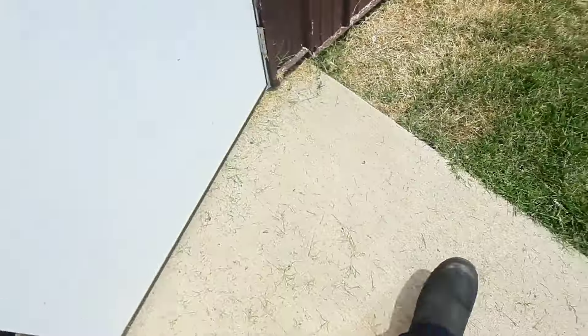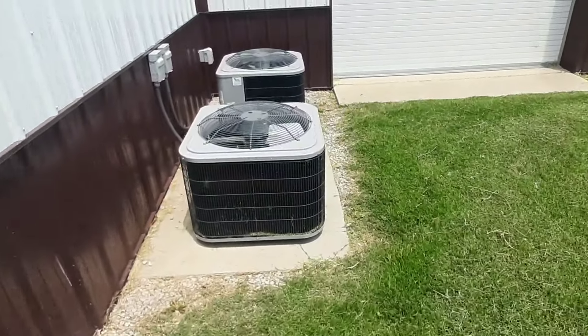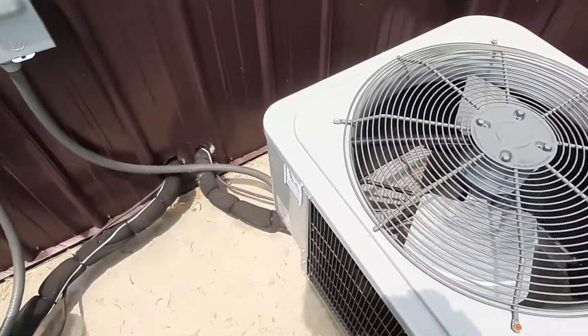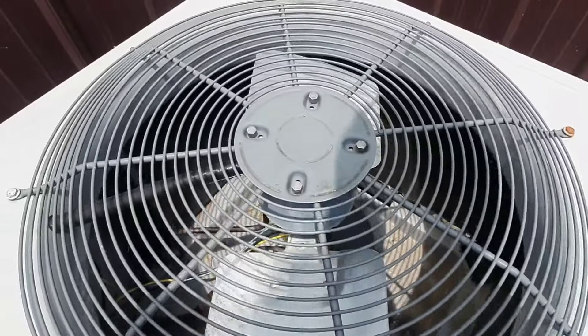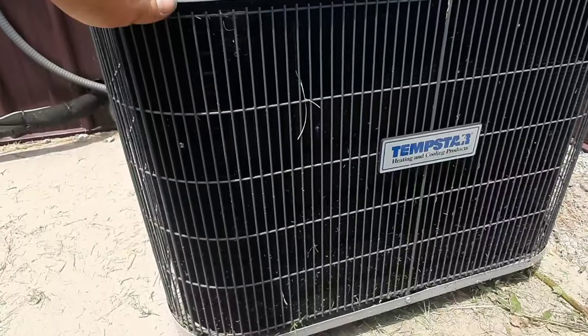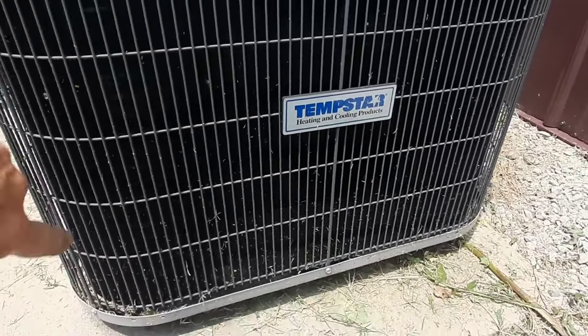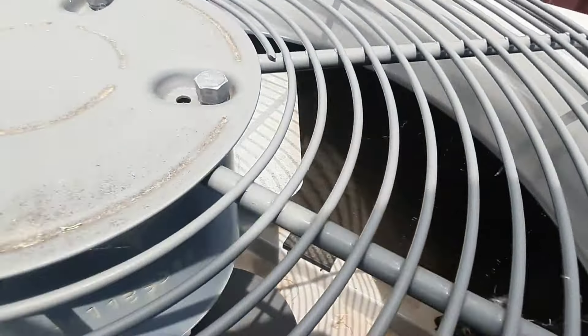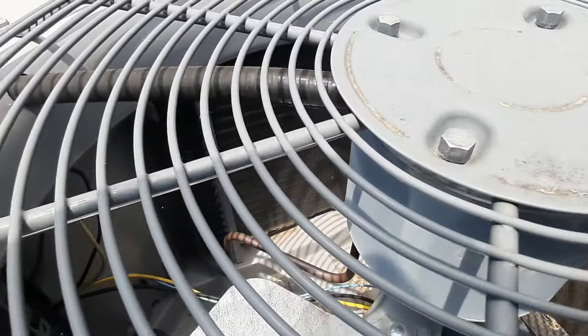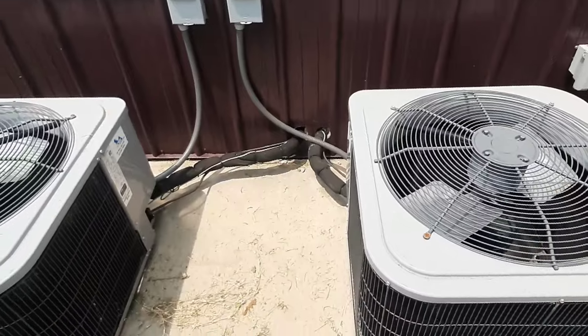Make sure we drop that door so I don't get locked out. My ACs are right here - nothing special, no safeties, just builder grade. These are just single coils, they don't look awful but we could probably use a clean. I can see some light through, so let's get our panels off, check voltage, kick them on one at a time and see what they feel like.